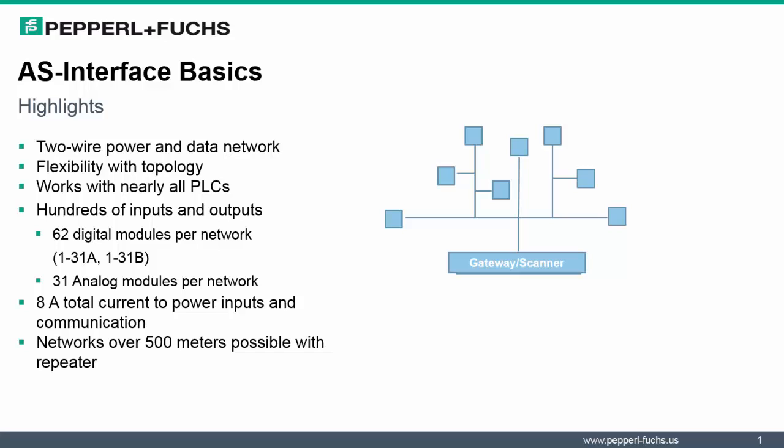AS Interface works with nearly all PLCs. The capacity of I/O counts varies. With the various addressing schemes, you could have up to 62 digital modules per network. There is also the ability to add analog modules to your networks as well. 8 amps is the total current to power inputs and communications. As you consider expansion with AS Interface, you could expand your networks for over 500 meters with repeaters.